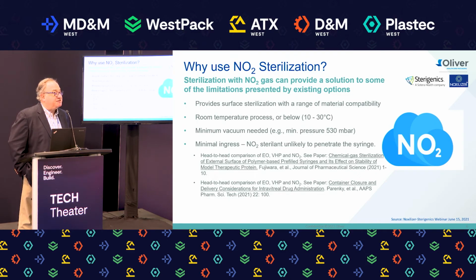And last, the benefit is the minimal ingress in terms of residuals. We've done numerous studies, estimate in the hundreds, showing that residual values of NO2 post-sterilization is way below the TWA or the safety limit as imposed by NIOSH and or regulatory authorities. Two publications that are key to comparing NO2 with the other methods are those listed on the slides, which you'll be able to find after the conference when you look at our reference on the web.